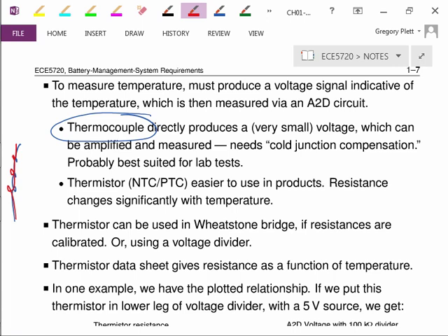If you read about thermocouples, you'll read about cold junction compensation, which allows us to calibrate the measurement. Thermocouple measurements are quite accurate, and the measurement changes quickly if the temperature changes quickly - there's not a lot of thermal momentum with a thermocouple, so it has rapid response. Because the voltages are so low, they're easily influenced by noise, and the need for compensation also makes the circuitry more complicated. So thermocouples are probably best suited for laboratory-controlled tests.